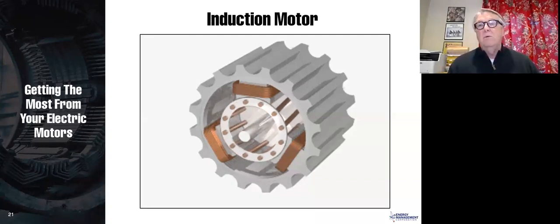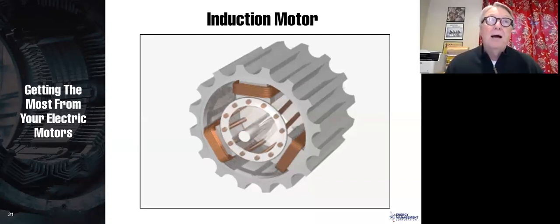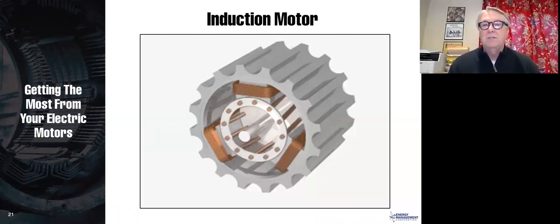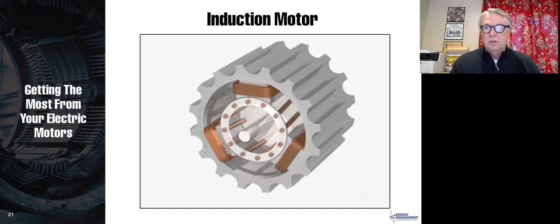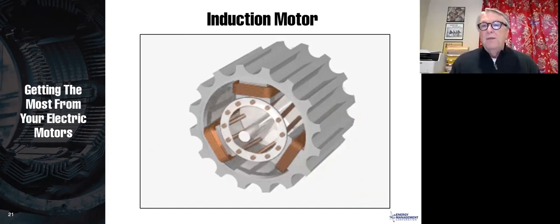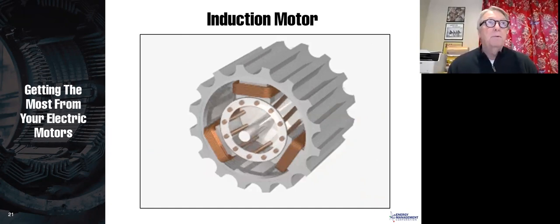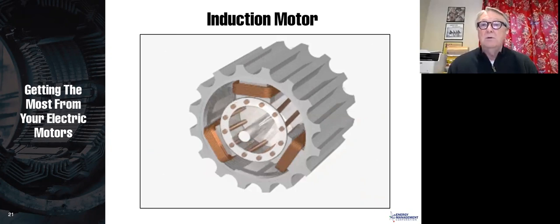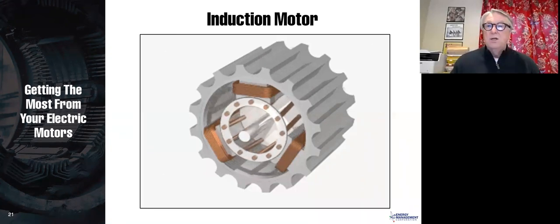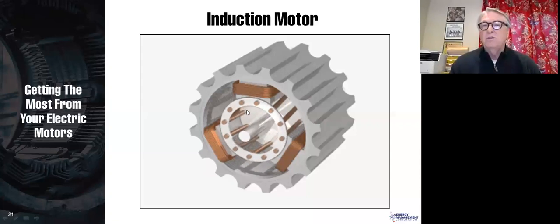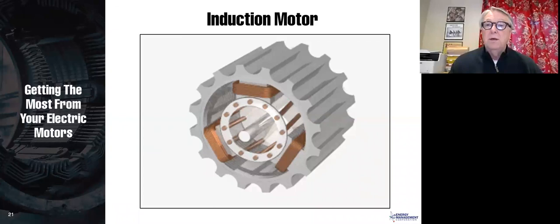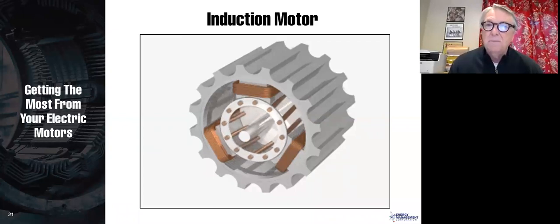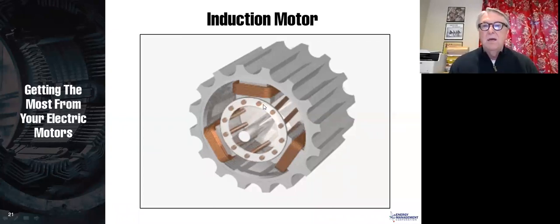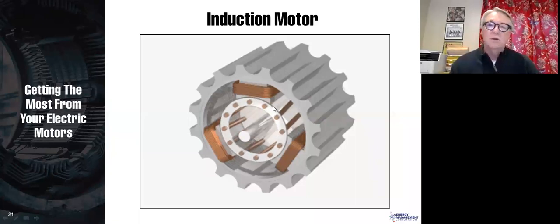That magnet on the rotor is induced by the flux on the outside of the motor on the stator, and therefore we call that an induction motor. One of the differences between a permanent magnet and induction is an induction always has to slip a little bit. So with a permanent magnet, the rotor is going to go exactly the same speed as the magnet on the stator. With an induction motor, that rotor is going to slip a little bit because it has to slip in order to induce currents in those rotor bars.